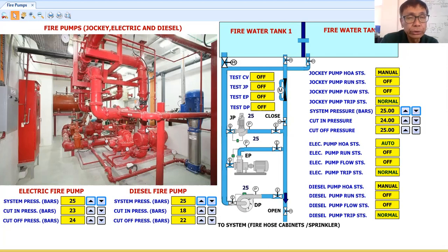Then, it is important that the system has an emergency backup like a generator, okay? Because we are expecting that when there is a fire scenario in a building, we might lose our main power supply or the normal power supply. So it is important that there is an emergency backup, okay? Now here, I don't need to explain all the necessary valves, gate valves, zone control valve, alarm check valve. I will not explain it to you because as I said, I am going to simulate these fire pumps from a BMS engineer's point of view, okay?